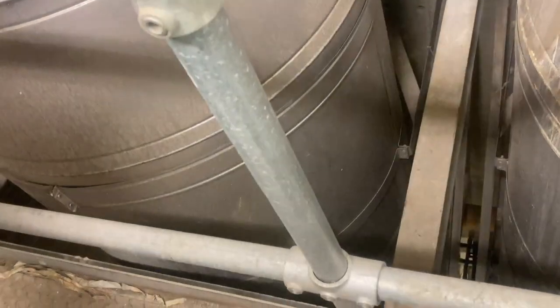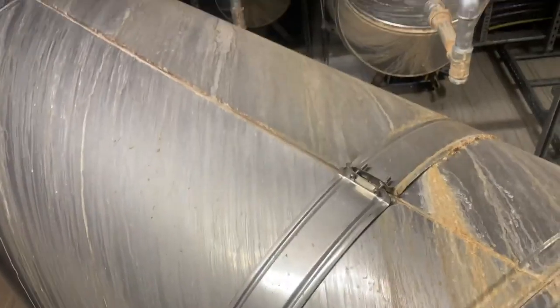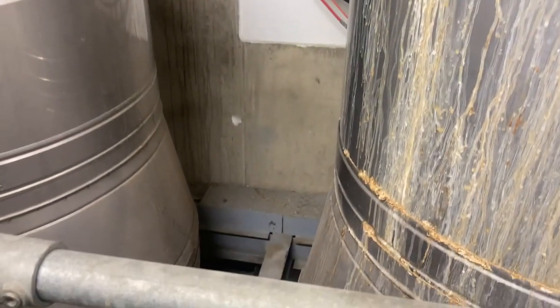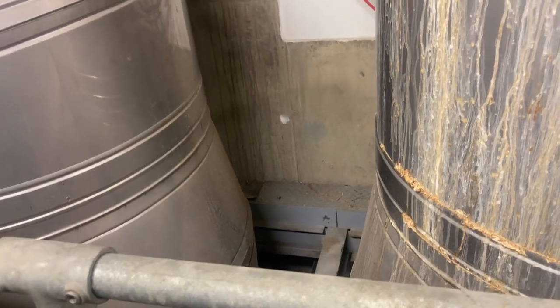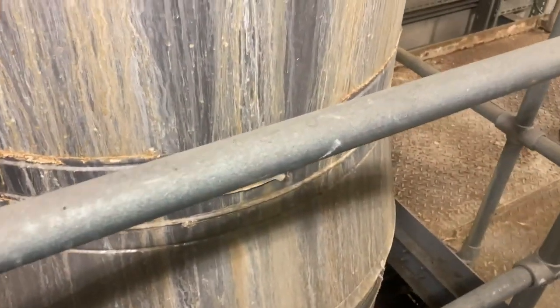Do you do any form of spillage test on these? Yes, we'll check. Well, it's just checking that the burner is working correctly, so the air pressure switches are working. I showed you the mechanical ventilation. So that's got the air pressure switches on there. So you wouldn't check for leaks or anything on this then? Visual. Okay, and then check the termination.